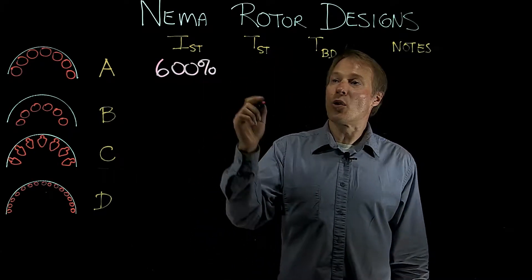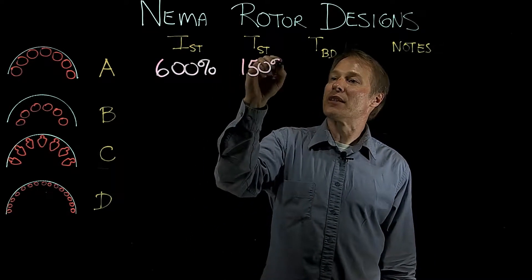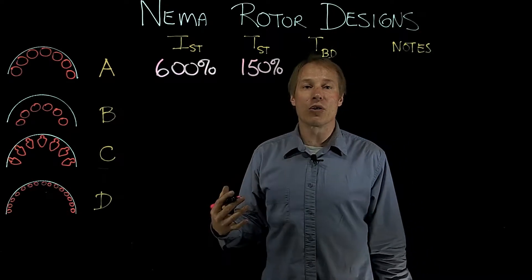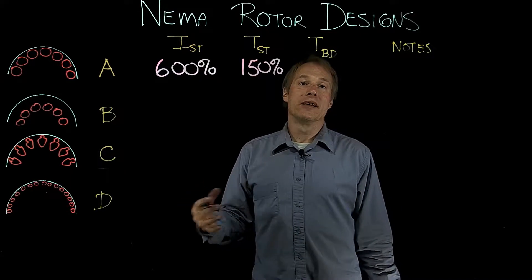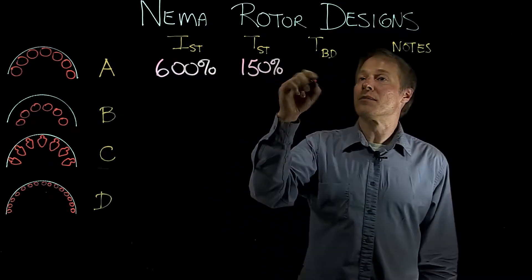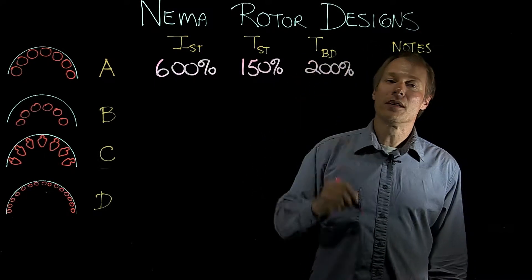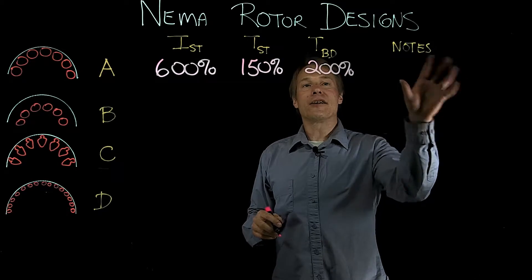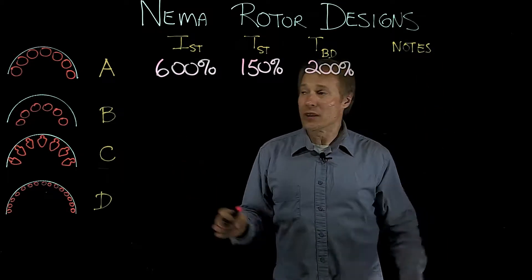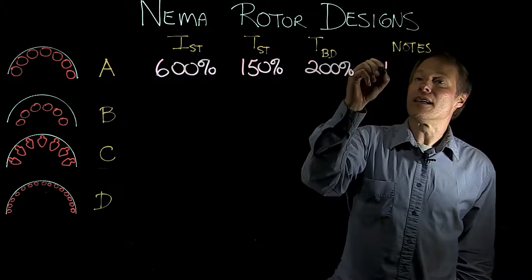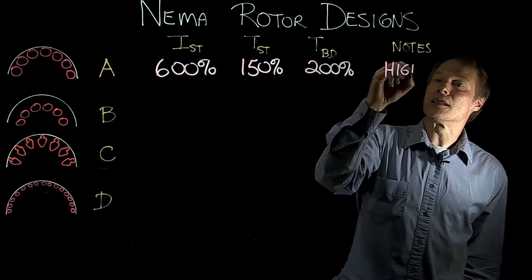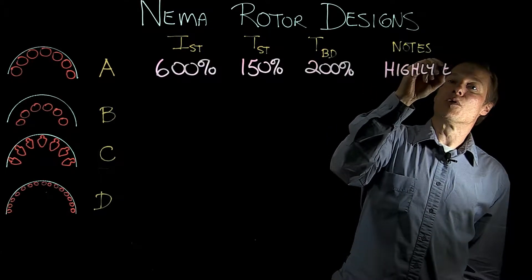Now the starting torque is going to be about 150% of the full load torque, whatever that may be. Now the breakdown torque, that's our peak torque, that's going to be about 200% for this motor. And the characteristic of the NEMA A design is it's highly efficient. So it's the most efficient rotor design.